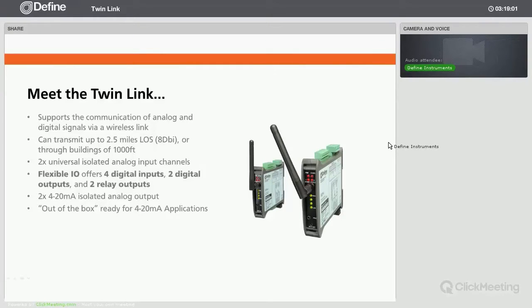The other great thing about the TwinLink is that anyone who is familiar with 4 to 20 milliamp signals can set up and use these units. They are that easy to use. We call them out of the box ready, and this means that all you have to do is turn the units on. They are already set up for 4 to 20 milliamp in and out, and there is no setup or configuration required.